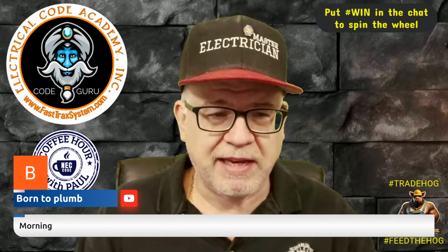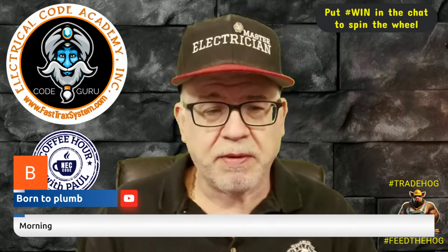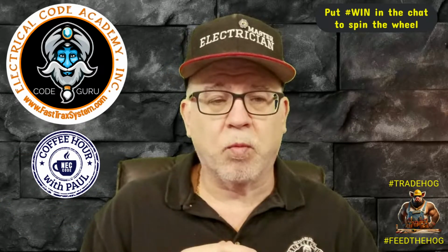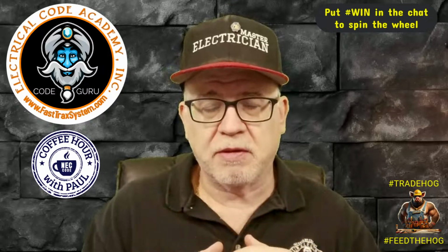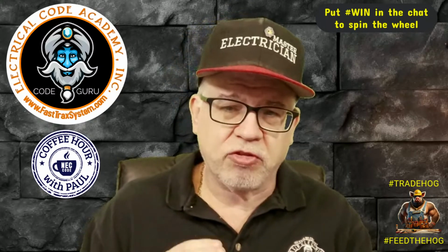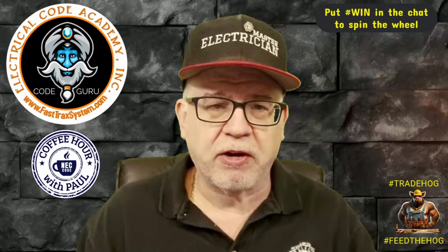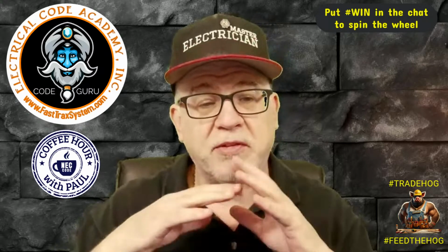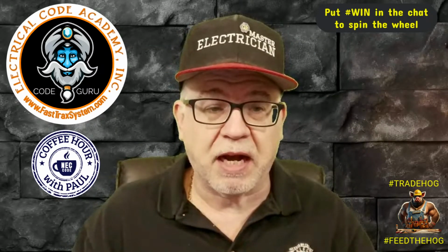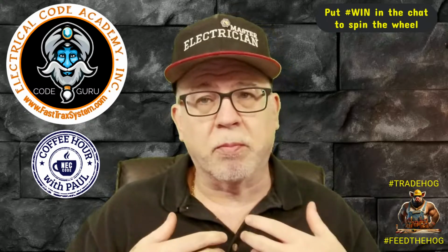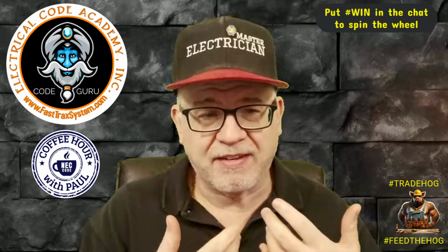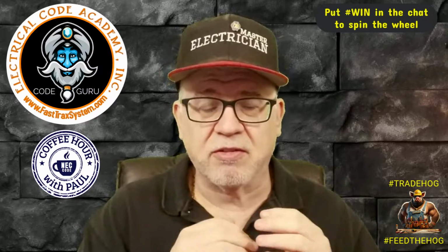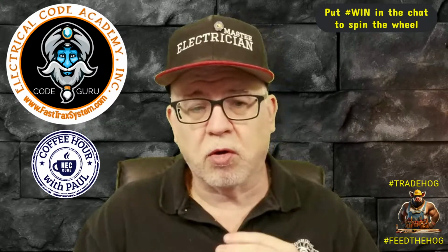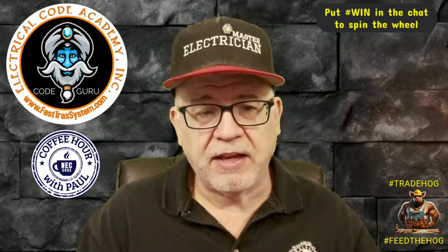I did get your question. I will cover it on a podcast, but I will tell you that typically those boxes that are part of a listed product, there's no stamping on them. What we refer to is the manufacturer's instructions, which are a part of what it was evaluated for. So when we think of metal boxes, we're pretty much bound to 314.16 for those standard type boxes. And non-metallic boxes will post the cubic inch values and things like that.